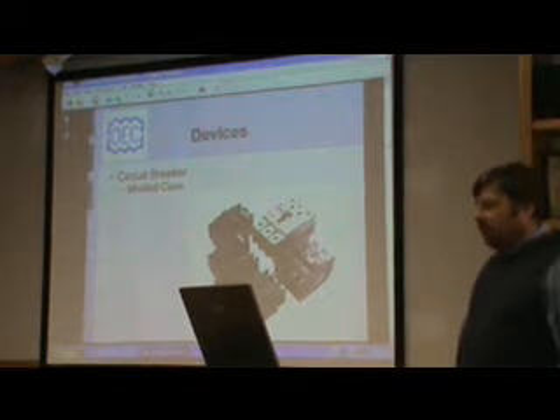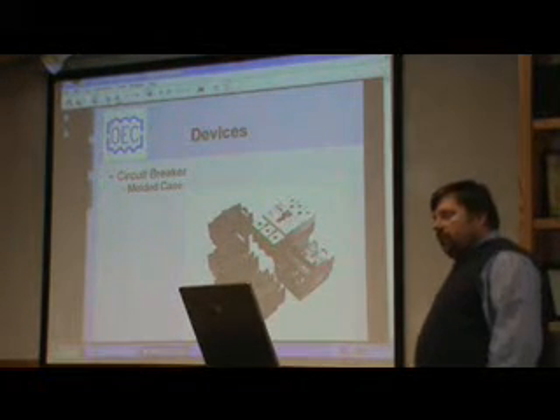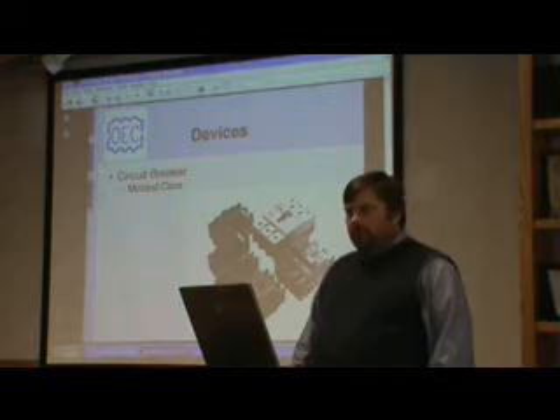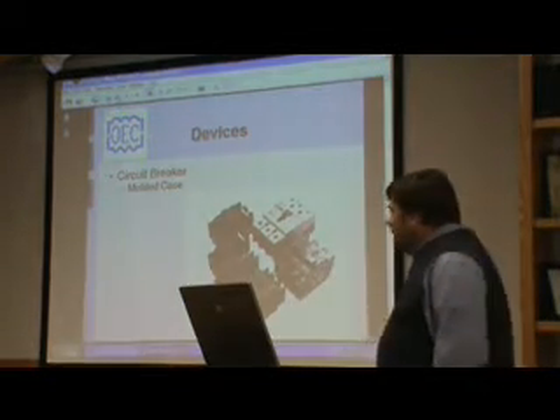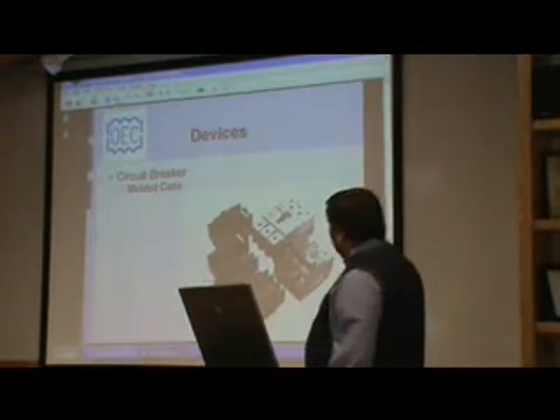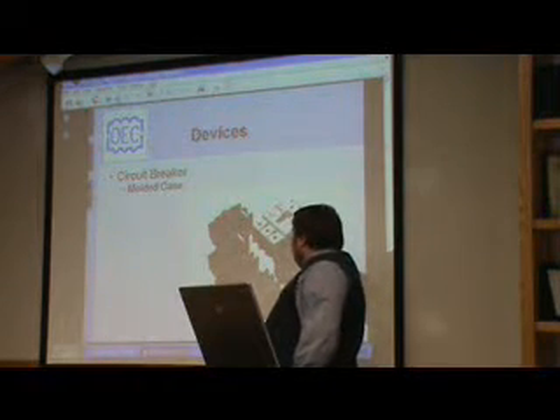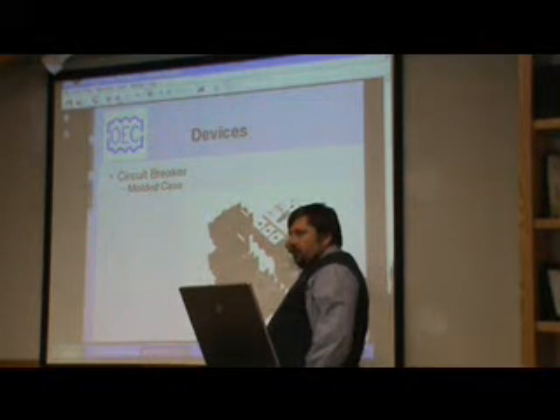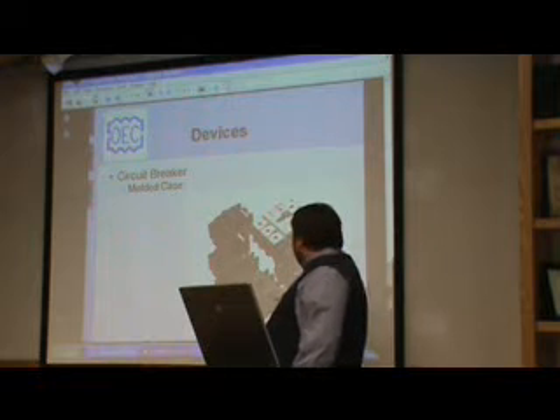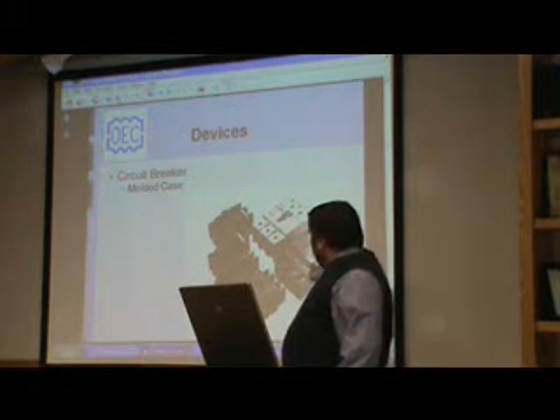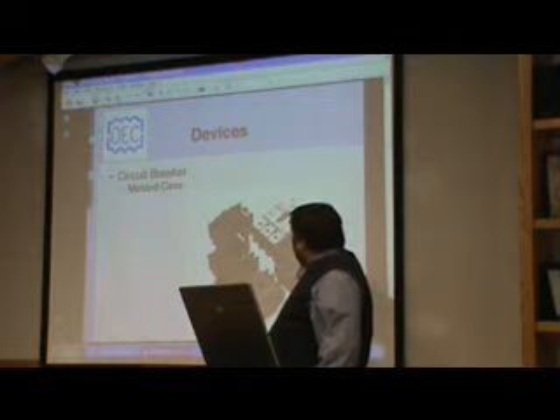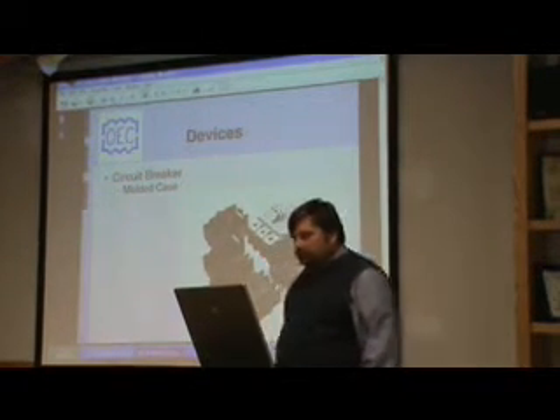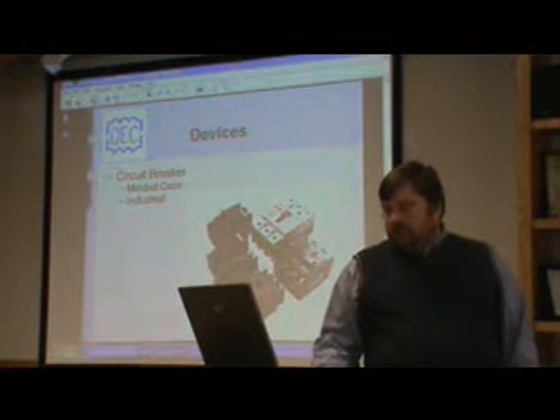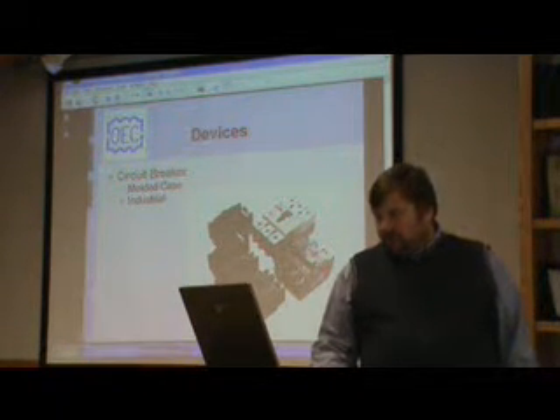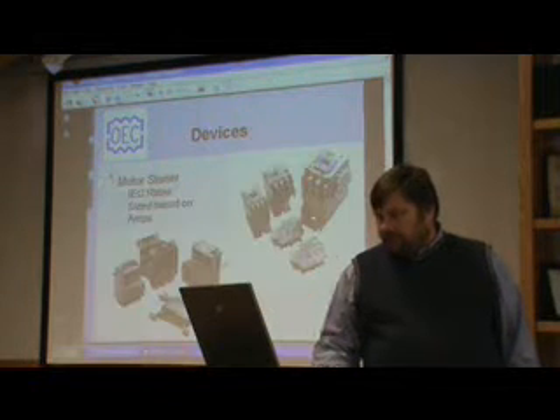We talked a little bit about circuit breakers. The circuit breakers that we use in our panels are what they call a molded case circuit breaker. It's for industrial use. We see a couple different examples here. This white circuit breaker would be used for a 480 volt circuit. It's just a circuit breaker designed for that voltage. And in a lot of the residential stuff, you'll see these smaller black breakers, which we call the quick lag series of breakers. Again, they're all industrial strength type devices that are used in the control panels.